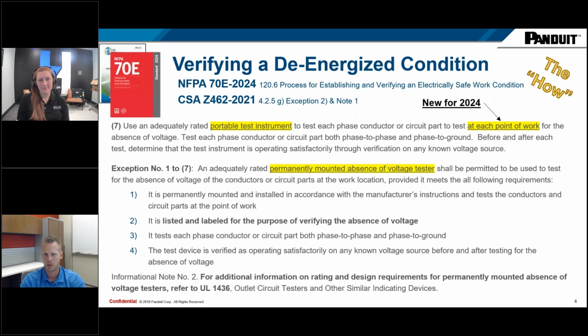Really just "at each point of work" was added. That had been in the blurb for absence of voltage testers since the first iteration, so we're improving the previous verbiage as well. So 2 methods, right? Portable test instrument, and then now using the absence of voltage tester, with the exception that it has to be installed in accordance with the manufacturer's instructions. Pretty straightforward. That's anything from a wire nut to a dishwasher. You have to install it based on how the manufacturer says to do it, how it's designed.